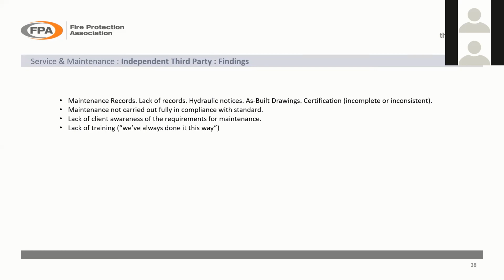Lack of training for people who carry out the in-house tests themselves, the weekly testing of the pumps, and that we've always done it this way, or we've been shown how to do it this way. So bad habits breed bad habits. What you need to do is have a refresh, get yourself trained up again, and then it'll make sense. I think a lot of times you see people do a tick box exercise where they read a couple of pressures, put them down, or maybe even write the same pressure down that they had last week without checking the gauges. Very important that the staff trained to do it know exactly what they're doing, what they're recording, why they're recording, because you rely on this system in the event of a fire. And if it doesn't work, it could well be because it hasn't been maintained correctly.